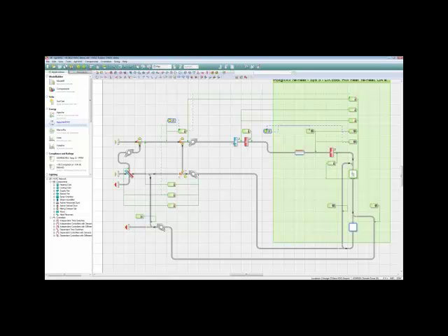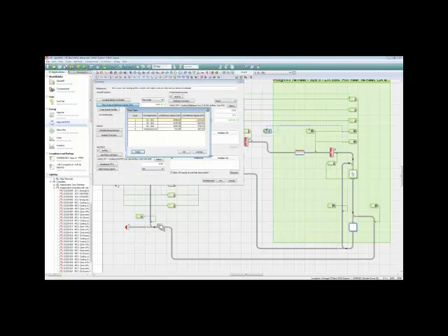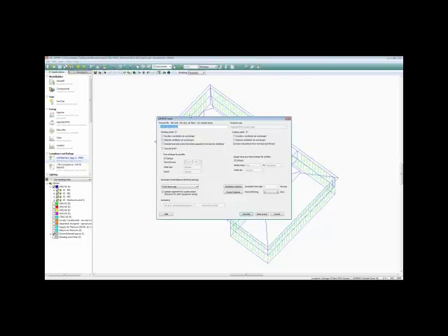And so moving along in the new features, why don't we finish the sizing process? We did the zone level sizing. Again, in the system level sizing, we're now going to size boilers, chillers, fans, and so forth. This defaults to the system that I had open. But this could be any system. I could say, nope, I want to go size this one right now. Or I could run this multiple times and size several different system files. So this is just pointing to a file which may have any number of systems in it. So go ahead and calculate.